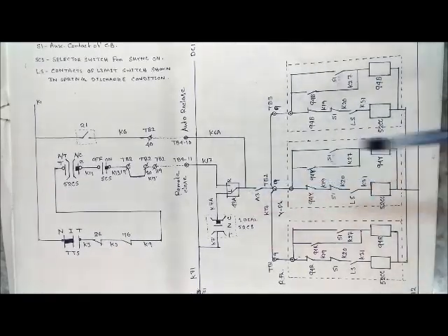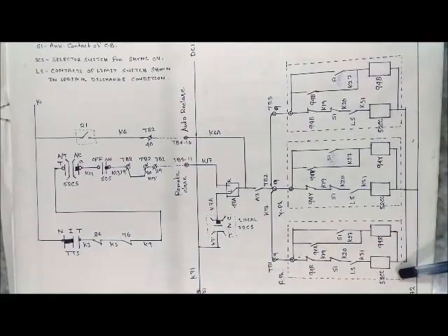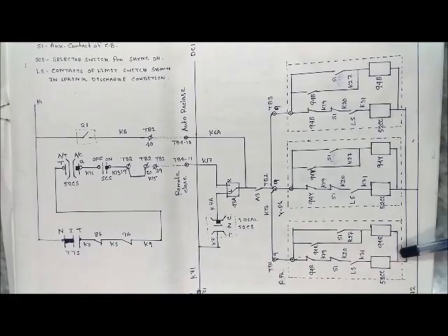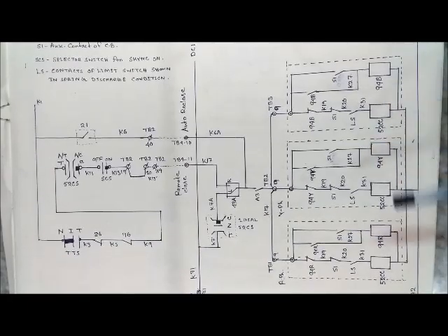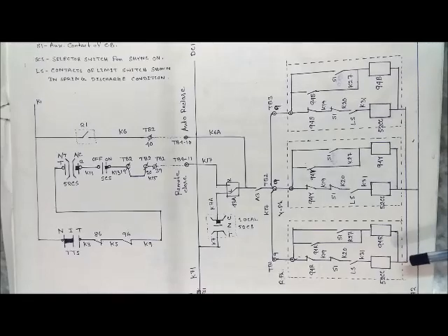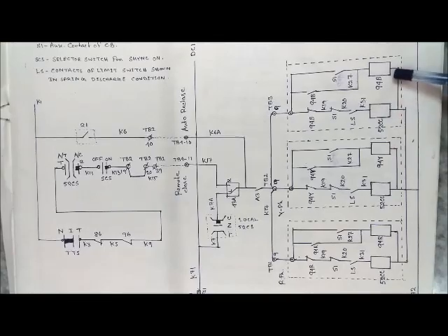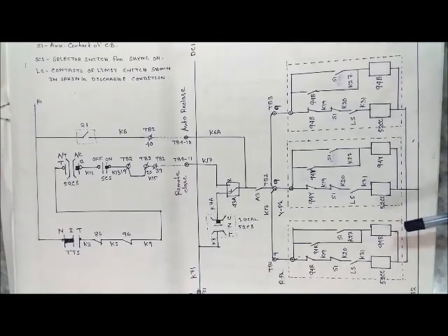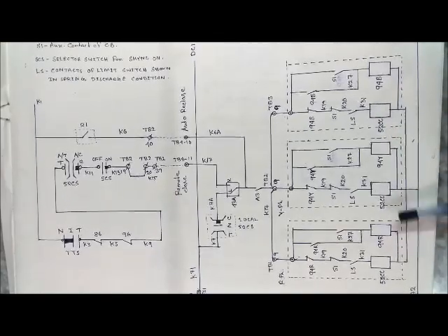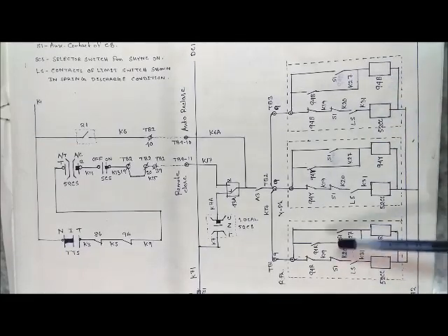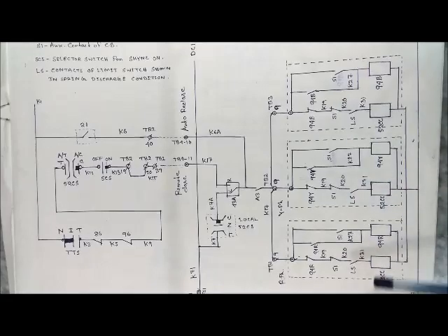If the gas pressure is above 7.8 bar, this contact will be in NC position. 52CC is the closing coil of the circuit breaker. In case of 220kV and above rated circuit breakers, there are three separate poles — R phase, Y phase, and B phase — and therefore in each phase there is one closing coil. 94R, 94Y, and 94B are the anti-pumping relays for R phase, Y phase, and B phase of the circuit breaker.